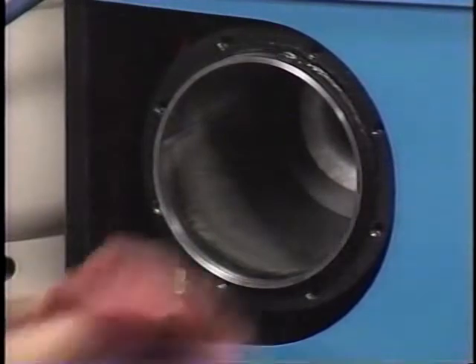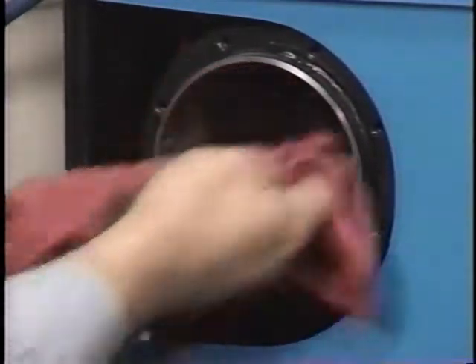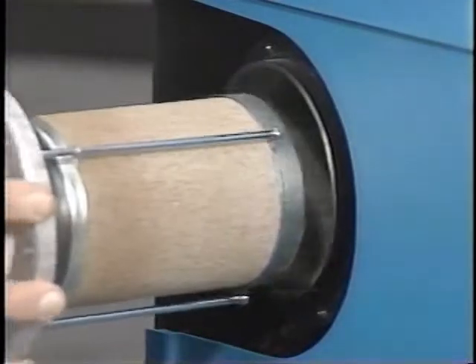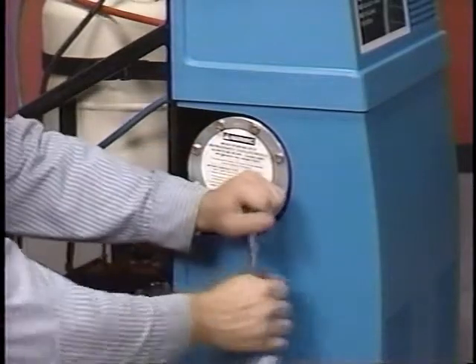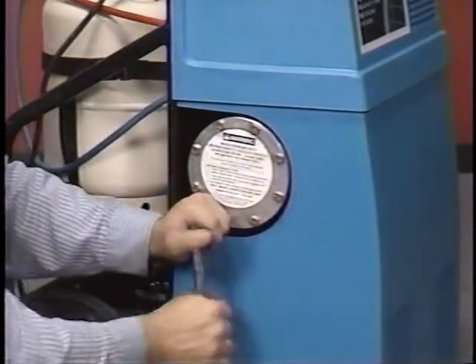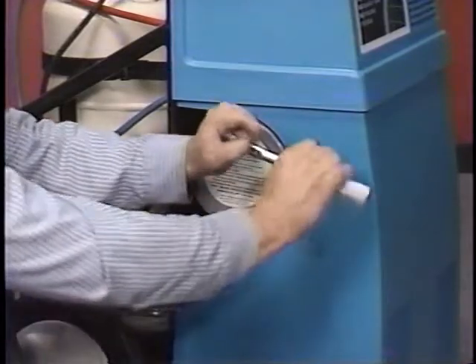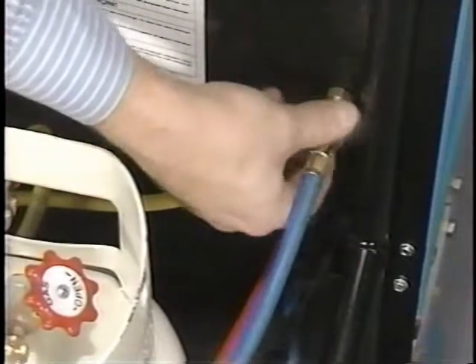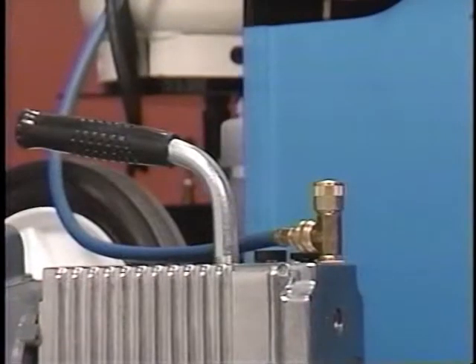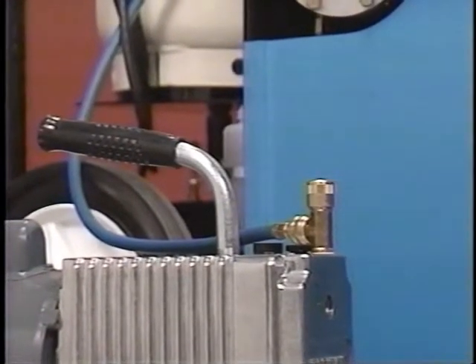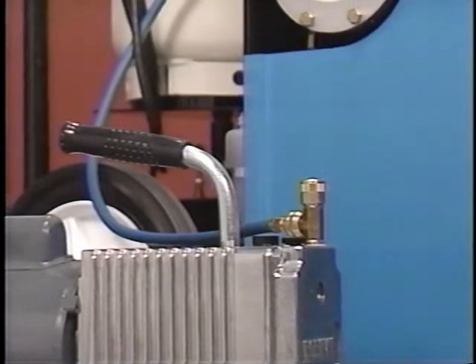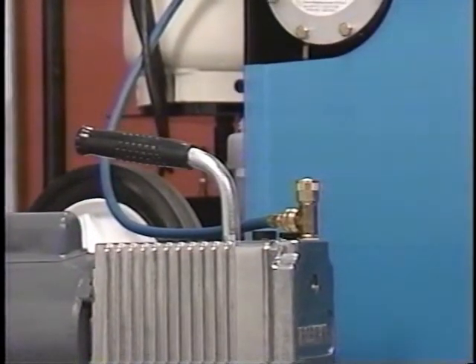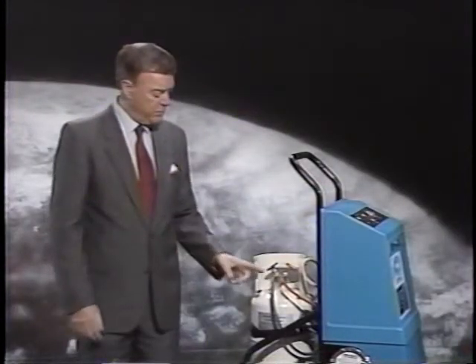cap, and filter core assembly. Clean all the internal parts with a dry towel. Insert the new filter assembly into the filter shell. In a star pattern, torque the bolts. Next, remove the blue hose from the inlet and attach it to a vacuum pump. Run the vacuum pump for 10 minutes to remove air that entered the unit during the filter change. After evacuating, attach the blue hose back to the liquid port and open the liquid valve. The system is now ready to continue recycling.